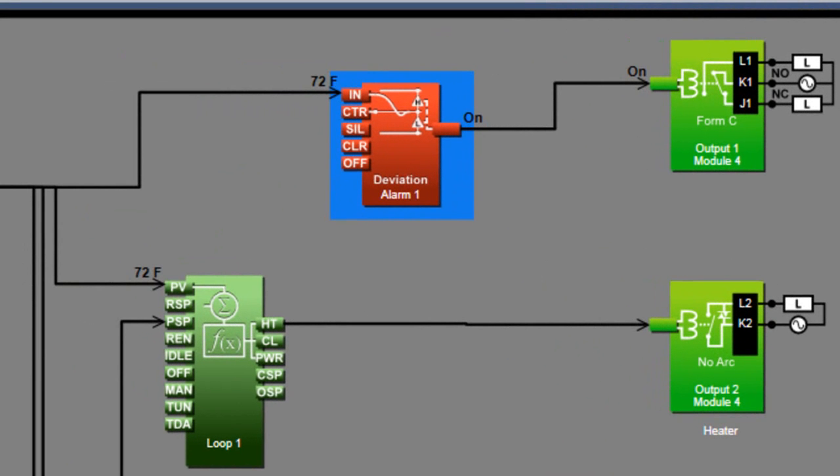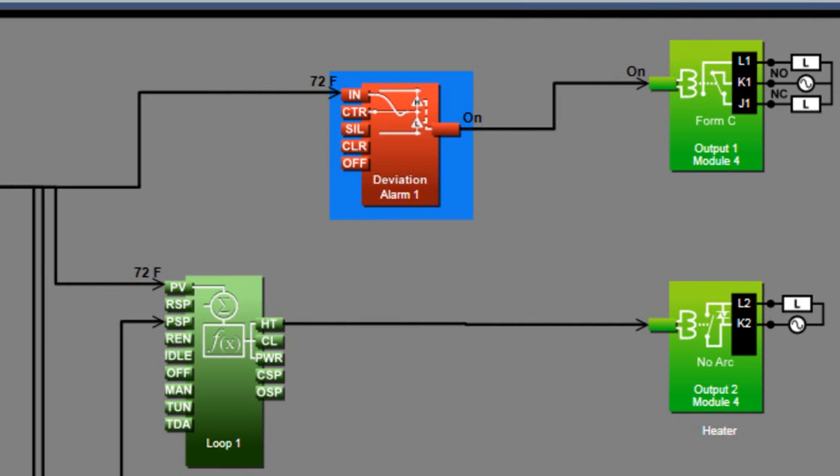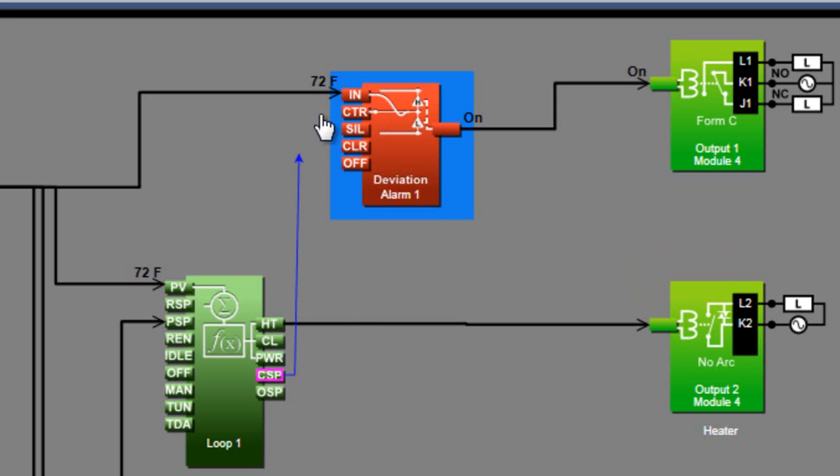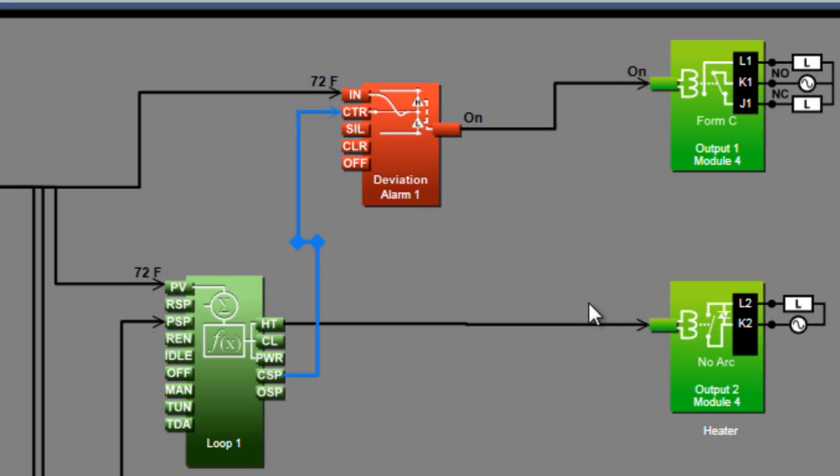The deviation alarm requires an additional signal that determines a center value, and the high and low alarm setpoints are set relative to that. Typically, you want the deviation alarm to be relative to a control loop's setpoint. When the alarm's type is set to deviation alarm, the CTR receiver becomes available. Connecting the control loop setpoint transmitter to the CTR receiver makes the alarm setpoints relative to, and centered on, the loop's setpoint.